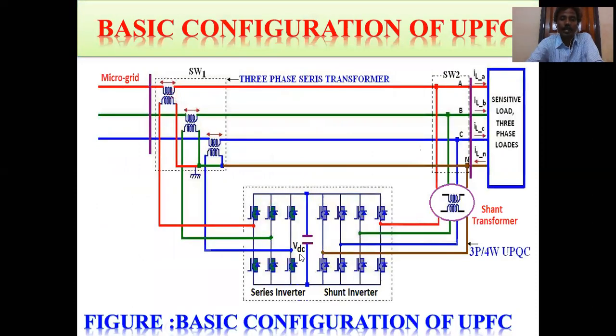Combined series shunt compensation FACTS controller. Series and shunt compensation at a time, a series and shunt connected compensator. This is the unified power flow controller. What is the configuration? This is the basic configuration of the unified power flow controller, UPFC or UPQC. If the transformer is absent, this is the UPQC.